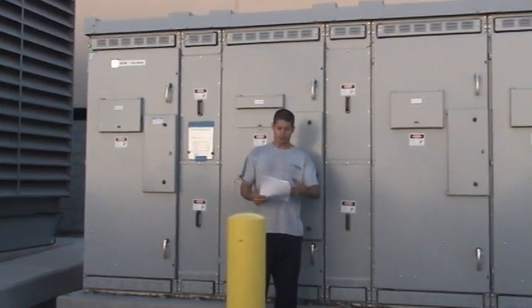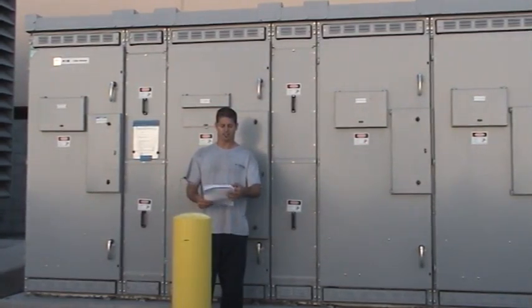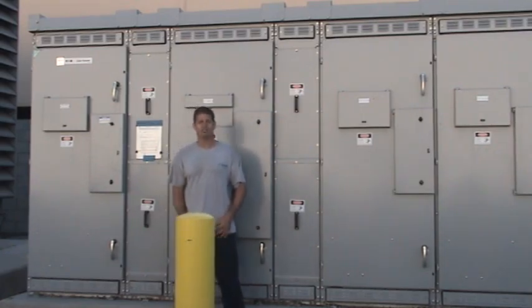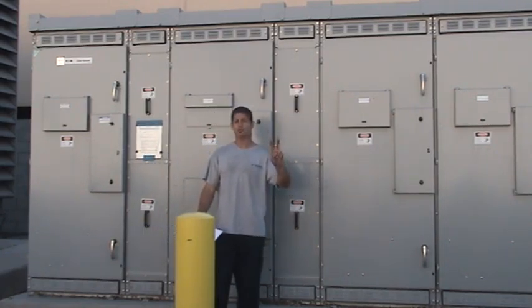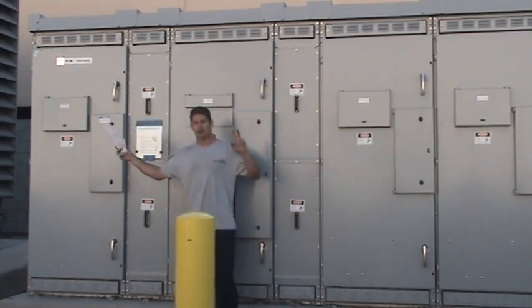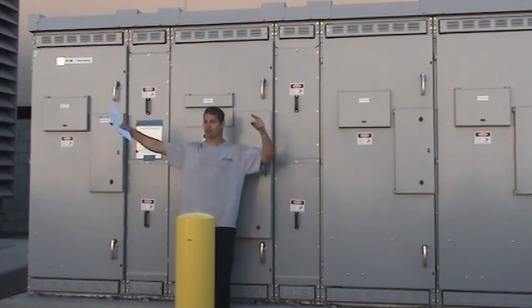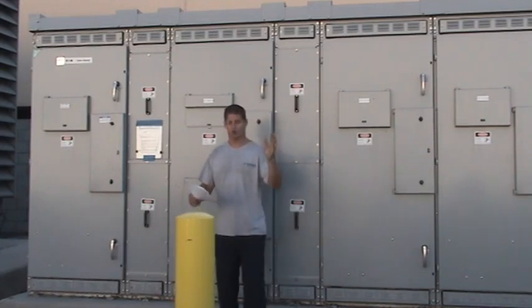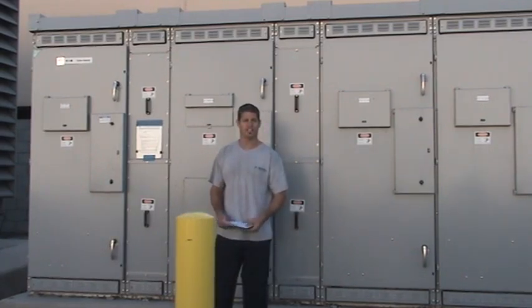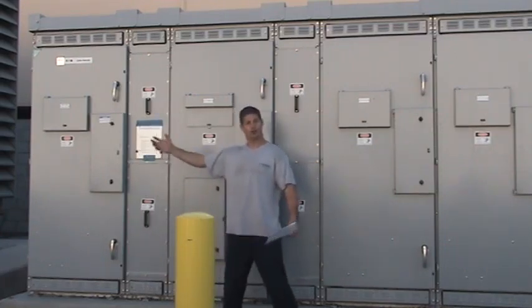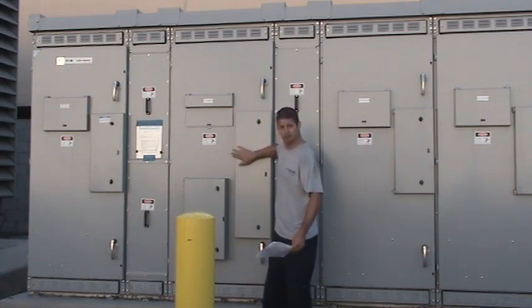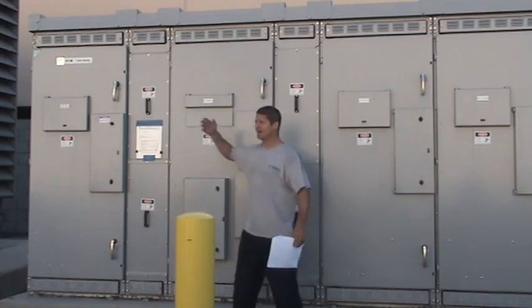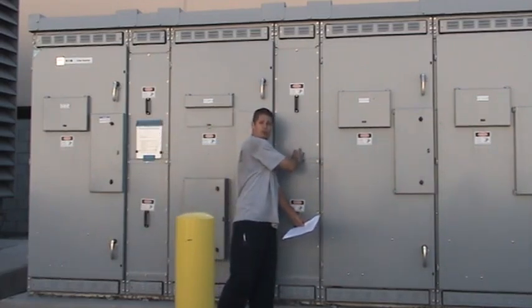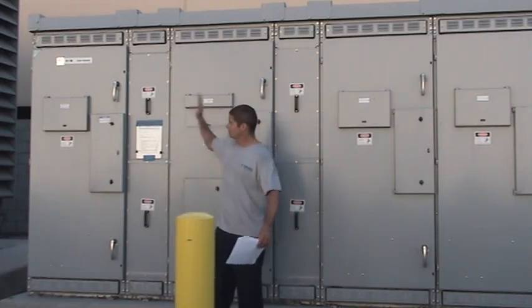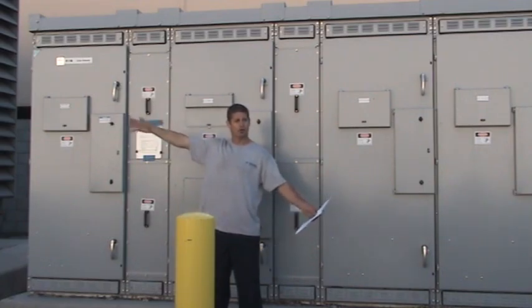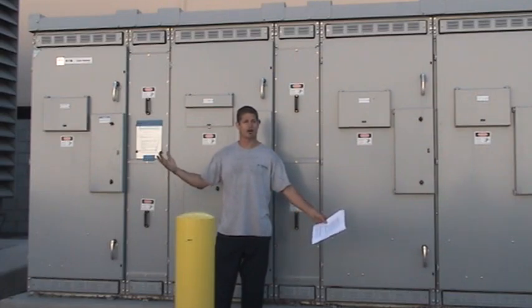Basically, I don't think we need to go through every line item on it, but it states what's going to happen in all different scenarios. You have 2 parallel power feeds coming from RP4, one goes to one side and one goes to the other side of your building over here. Now, if one should go, that's the first loss of voltage on MSV13. If one side should go, it will transfer over and pick up power automatically from MSV14, which is this switchgear. And vice versa. If this one goes down, if there's a problem with power on this side, automatically it'll switch over and pick up power from the other side. So that's your first line of defense if you have power trouble.